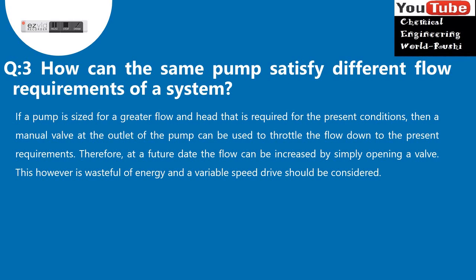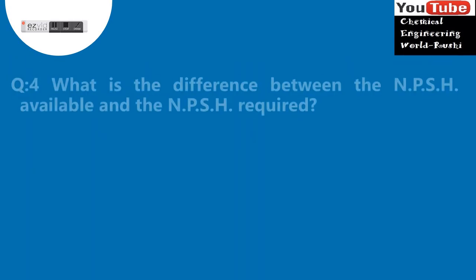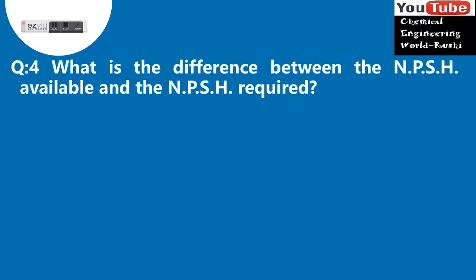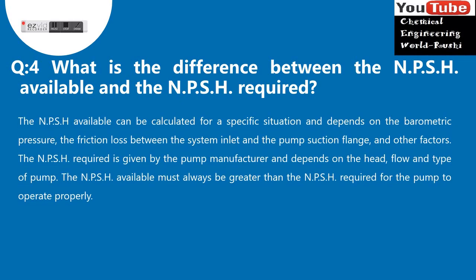Question 4: What is the difference between the NPSH available and the NPSH required? The NPSH available can be calculated for a specific situation and depends on the barometric pressure, the friction loss between the system inlet and the pump suction flange, and other factors. The NPSH required is given by the pump manufacturer and depends on the head, flow, and type of pump. The NPSH available must always be greater than the NPSH required for the pump to operate properly.